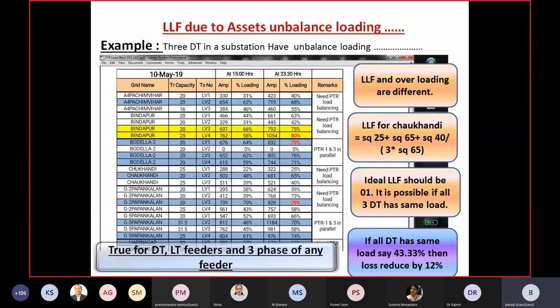This is true for the distribution transformer, true for the LT feeder, true for the three phases of a feeder - the load on all three phases should be equal. If there are 5 LT feeders from a transformer, all 5 should try to have equal load. Same with your distribution transformer.